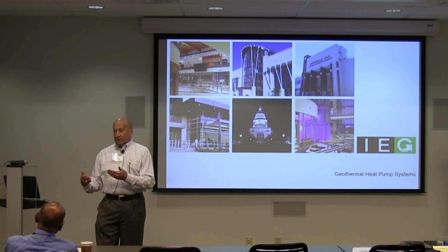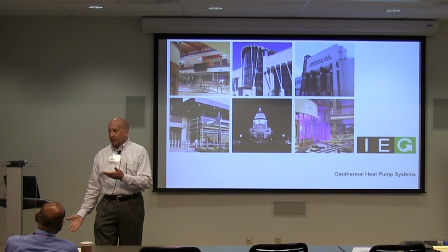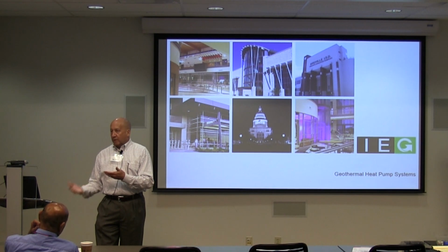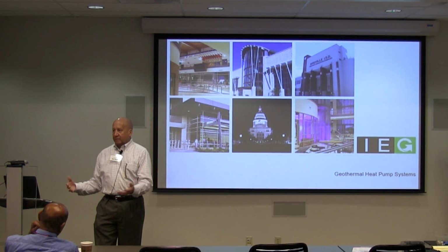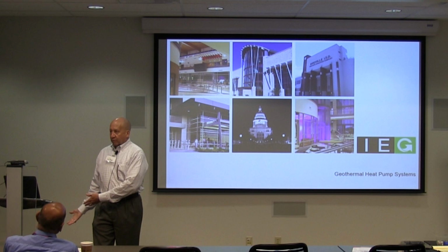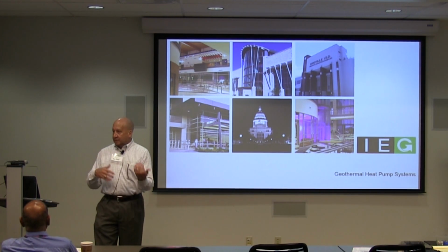I've looked at several projects where guys had a 1,400-foot well to get to an aquifer, and they wanted to lift the water. They had a 200-ton system and had to put a 75 horsepower pump on it to lift it and get the flow. So you start looking at your efficiency, your EER of the system, and you end up down in single digits real quick. It's just not viable.